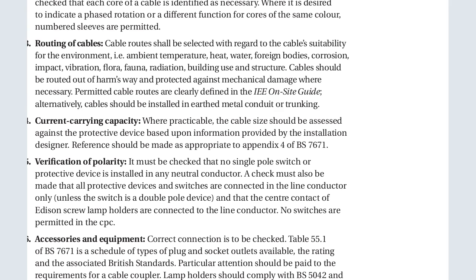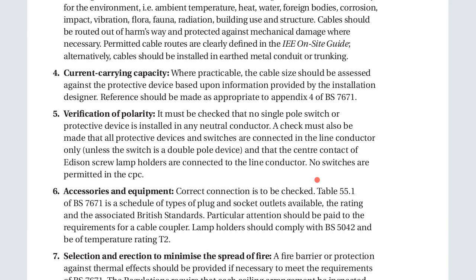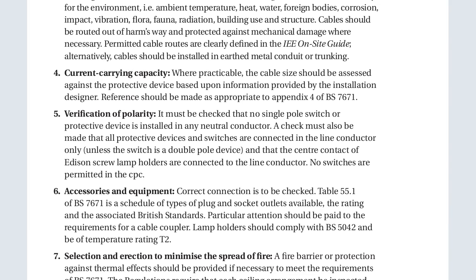So in checking the polarity, we are making sure that all the switches and all the protective devices are not installed in the neutral conductor, because the neutral conductor is not the live. When you install them in the neutral conductor, it will not work. So we have to make sure that all of them are installed in the live, which is also called the line conductor, unless the switch is double pole. When we have a double pole, we can have it on the neutral and the live. But if it is a single pole, we have to make sure that it is on the live conductor, and that the center contact of the Edison screw lamp holders is connected to the line conductor. So no switches are permitted in the CPC.